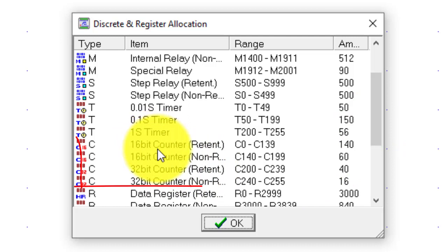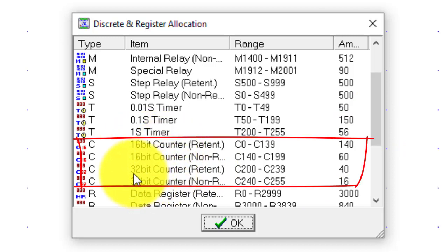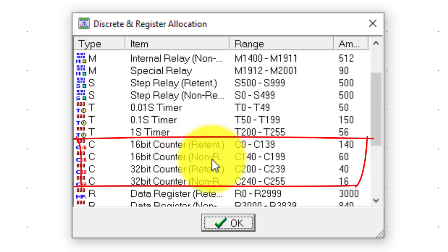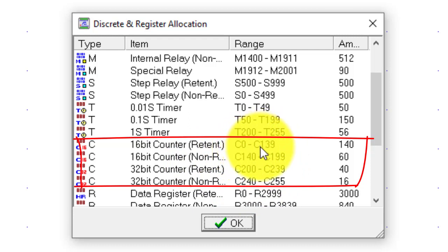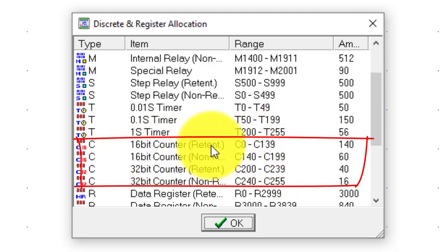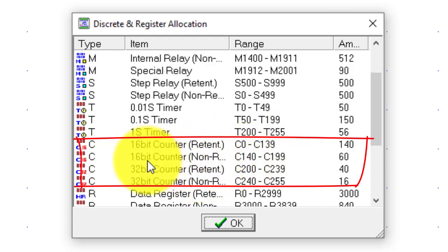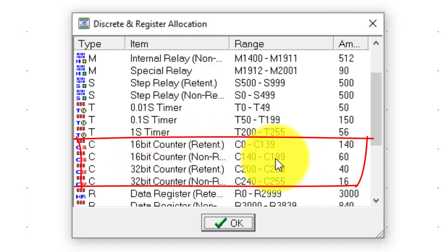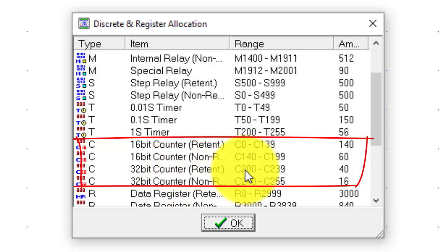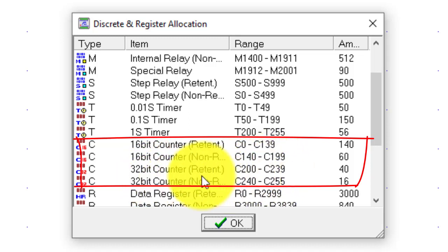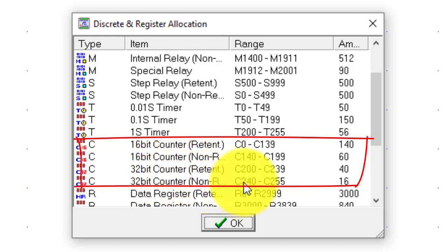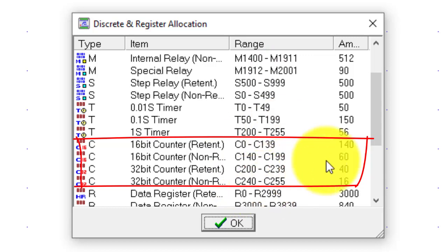Now for counter — you can see there are two types of counter: 16-bit counter and 32-bit counter, with modes retentive and non-retentive. The range C0 to C139 is the 16-bit retentive counter. From C140 to C199 the counter is 16-bit but non-retentive. From C200 to C239 is the 32-bit retentive counter. And the last one, non-retentive, is from C240 to C255.